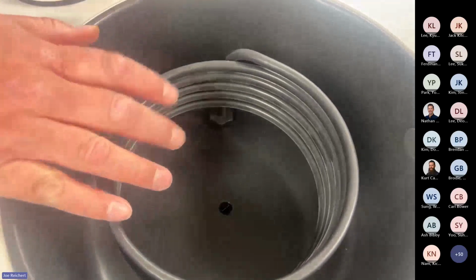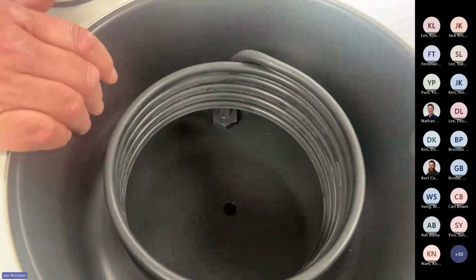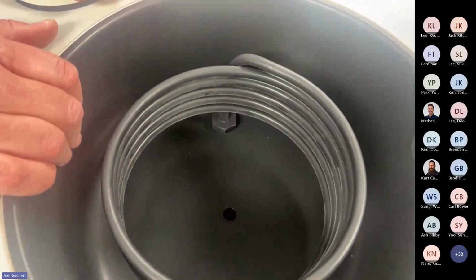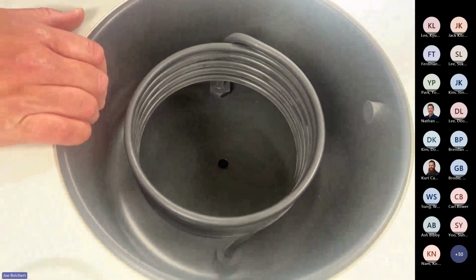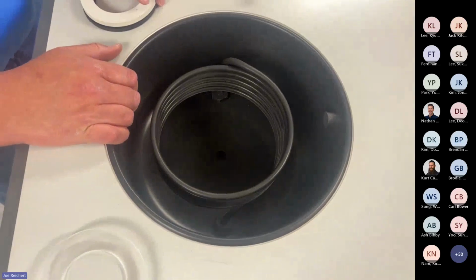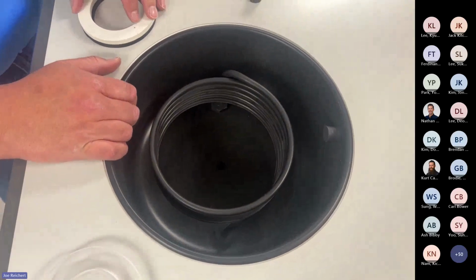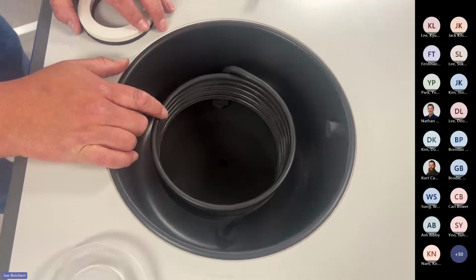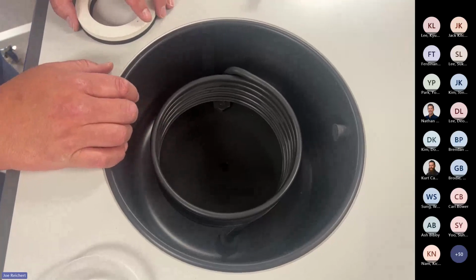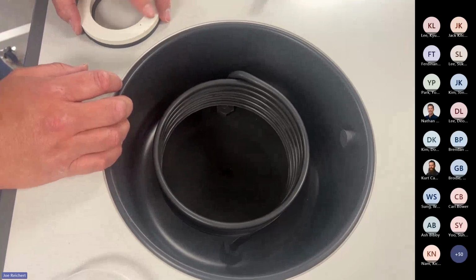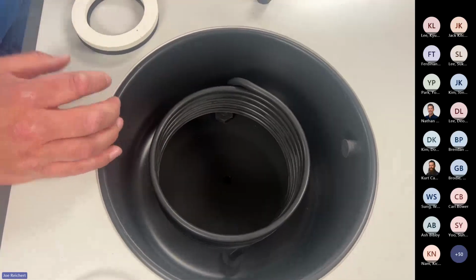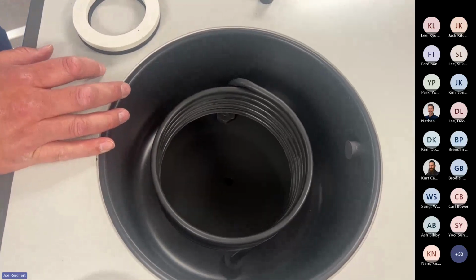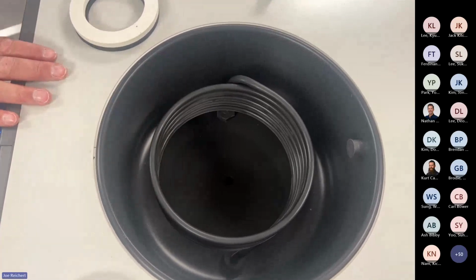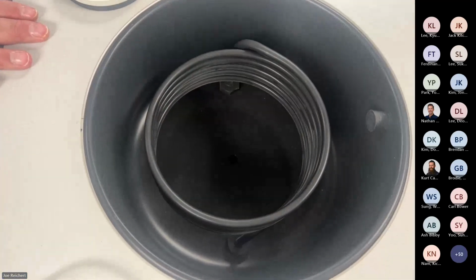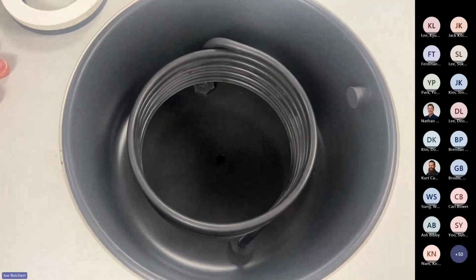But you can get holes in your chamber. This is a PTFE coated chamber, but we do have the stainless steel, and we sometimes have customers that will put acids in those or some kind of corrosive that might eat through the steel or pit the steel. You can get leaks like that in there as well. But also, you're not going to be dealing with just a vacuum leak on that. You're going to have a coolant problem on that machine. Okay, turn this off.